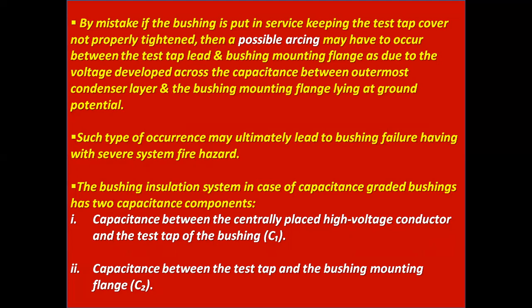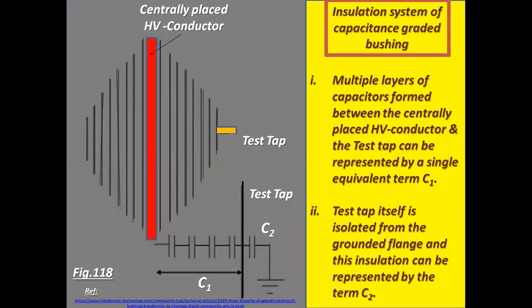The bushing insulation system in the case of capacitance graded bushings has two capacitance components. Number one, capacitance between the centrally placed high voltage conductor and the test tap of the bushing, that is C1. Number two, capacitance between the test tap and the bushing mounting flange, that is C2. Centrally placed HV conductor.